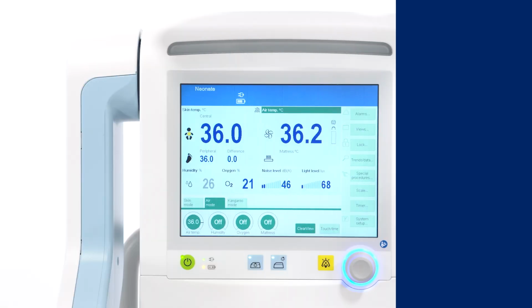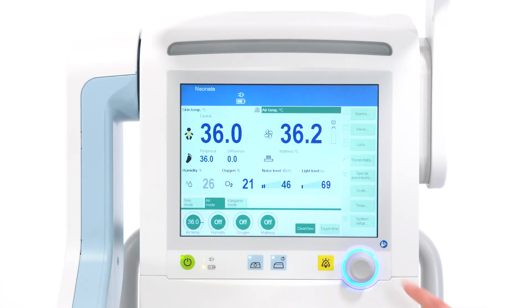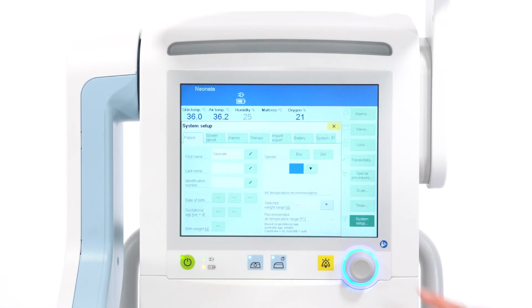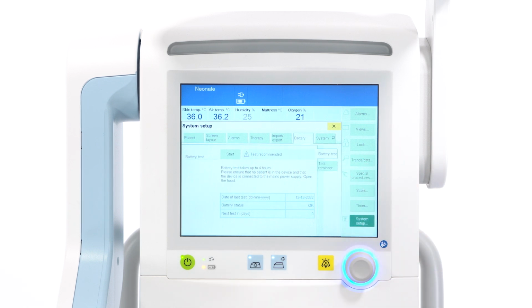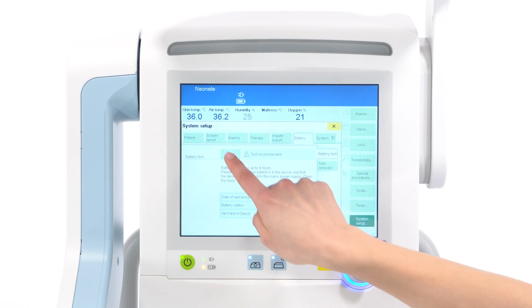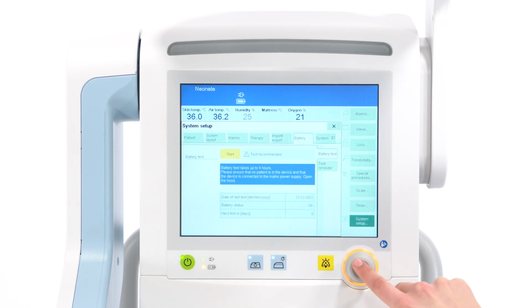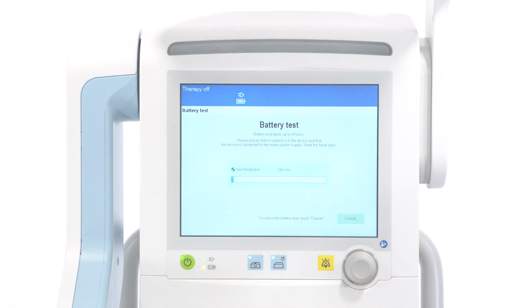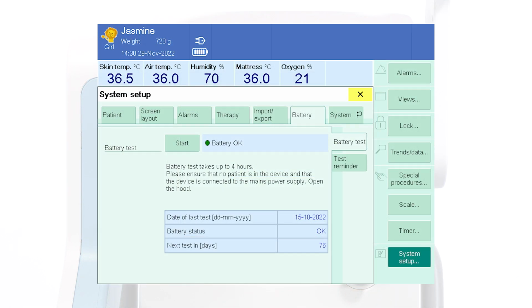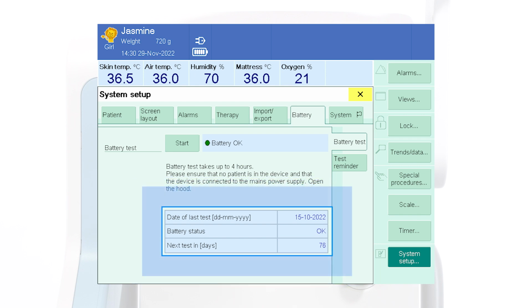Open the hood. To initiate the battery test, go to System Setup, Battery, then Battery Test. Touch the Start button and confirm with the rotary knob. After the test is completed, the test result is displayed: date of the last battery test, battery status, next scheduled test in days.